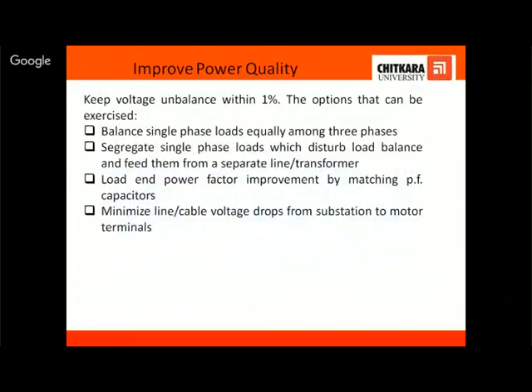Now, the voltage unbalance should be kept within a limit of 1%. The major options are: balance single phase loads equally amongst all three phases; segregate single phase loads which disturb load balance and feed them from a separate line or transformer; then improve load end power factor by matching the power factor capacitors; and minimize the voltage drops from the substation to the motor terminals. So either the appropriate size of cable should be chosen, or the distribution point should be near the motor terminal.